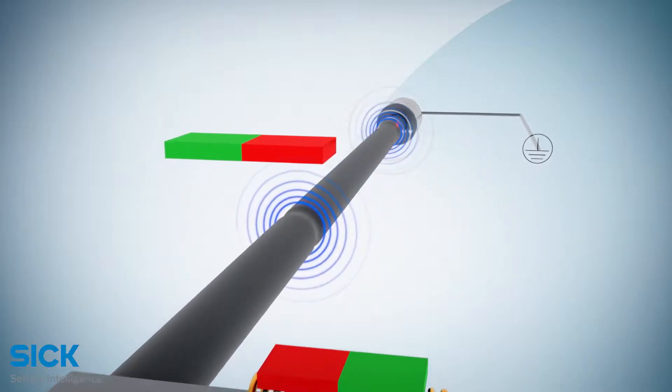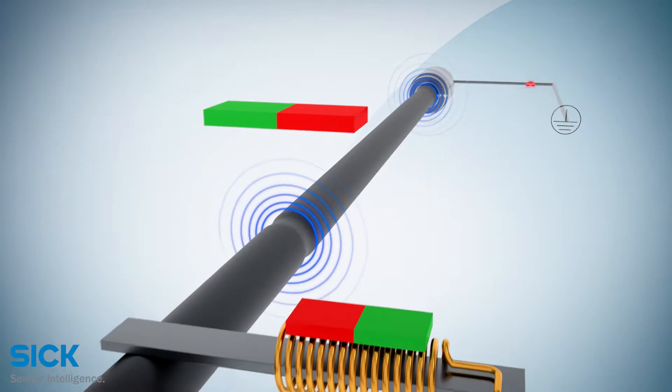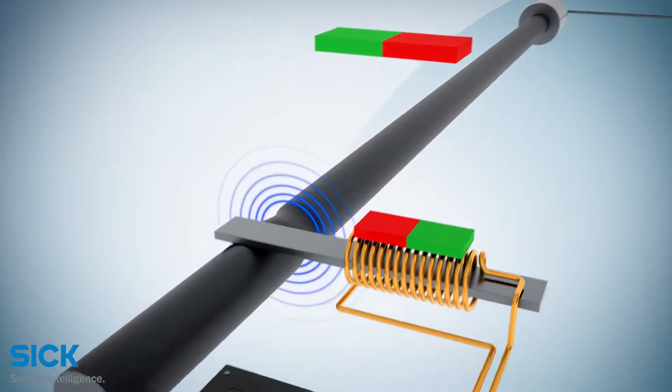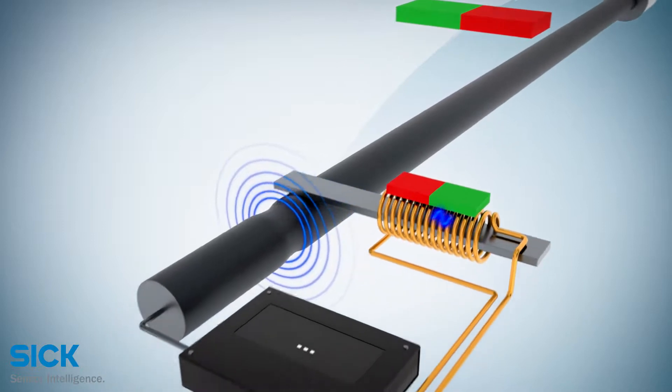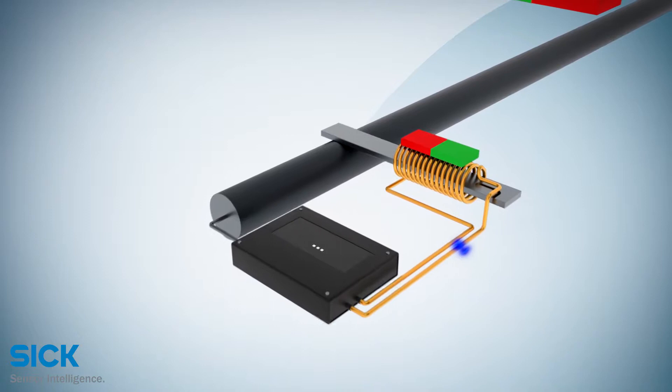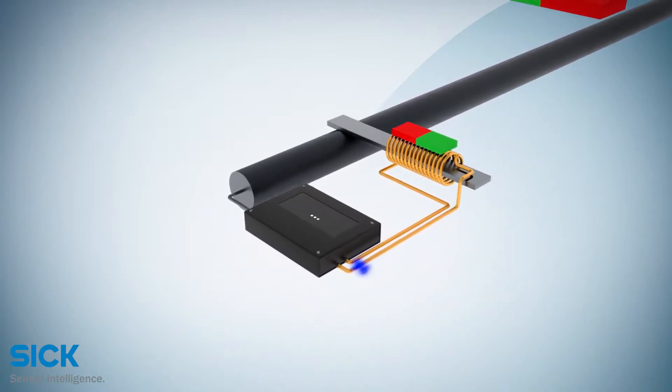To avoid disruption in the measurement, the strain pulse as well as the current pulse are damped at the end of the waveguide. The returning strain pulse in the direction of the measurement electronics is converted into an electrical signal by the pickup coil in the strain pulse converter.